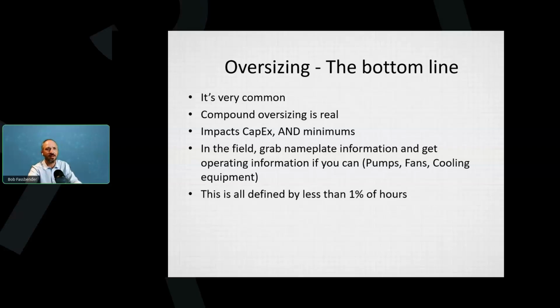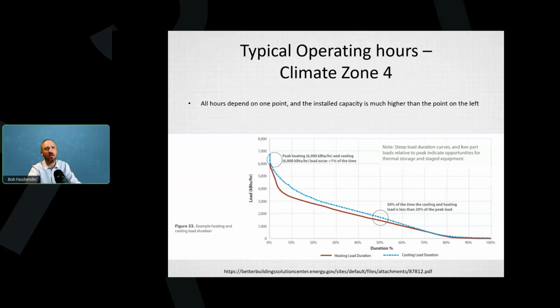So oversizing is defined by less than 1% of the hours. It impacts the rest of the year. So what happens the other 99% of the time? That's the next thing you need to know. Okay, so here we have, this is like climate zone 4. It's the number of hours spent in cooling and heating. And it takes a second to understand the chart, but the load increases to the left, and it's the percent of time that you're at high load and low load. And so if you look on the left, it's down to 0%. So in the 0.1% of time, you're at this area where you're at your maximum load.